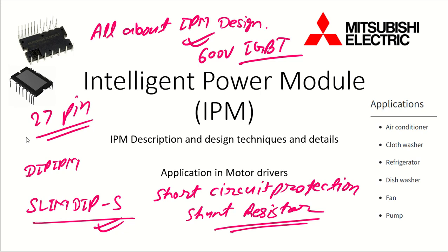Namaskar, my dear friends. As we are talking about intelligent power module (IPM) designs, we have taken an example from the SLIMDIP-S package, which is a DIP-IPM series. In this session we will be designing short circuit protection, and how shunt resistor design is very important. We will understand how to design the shunt resistor value for your application.